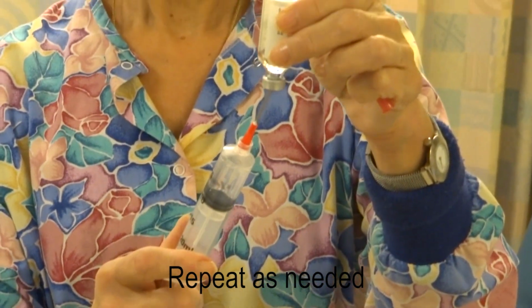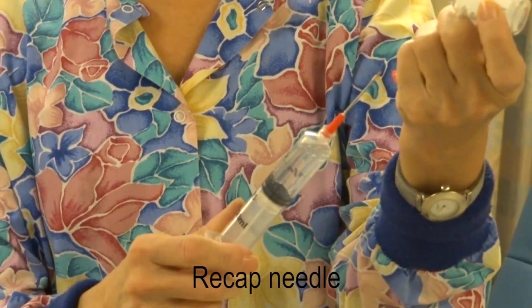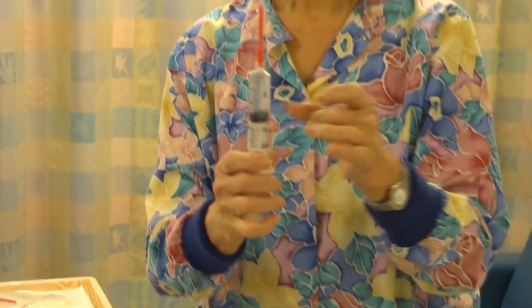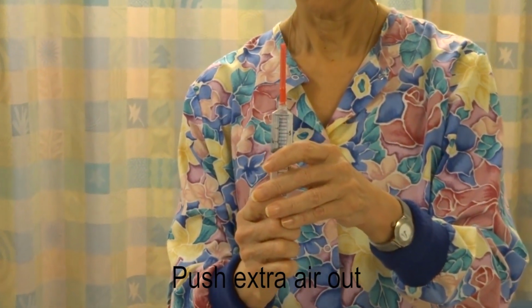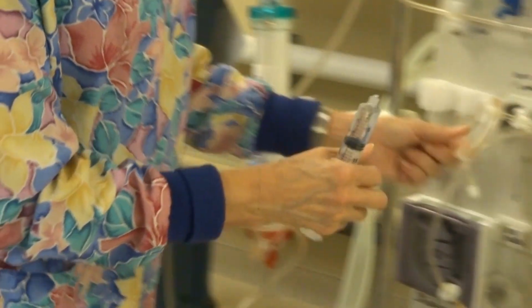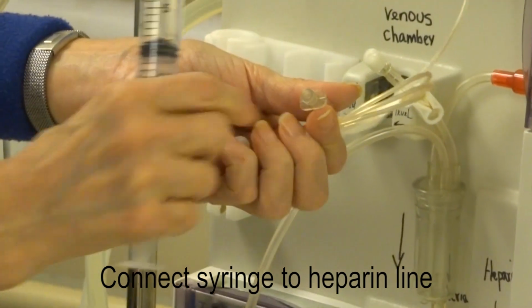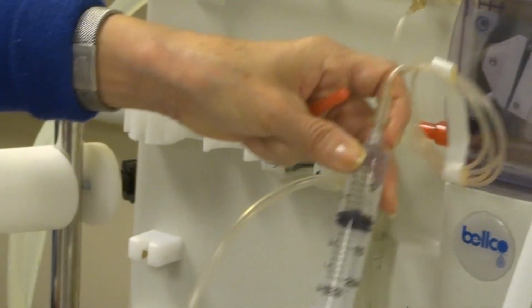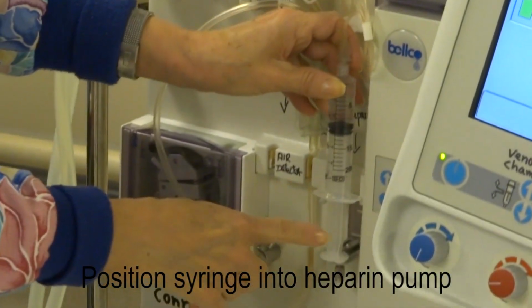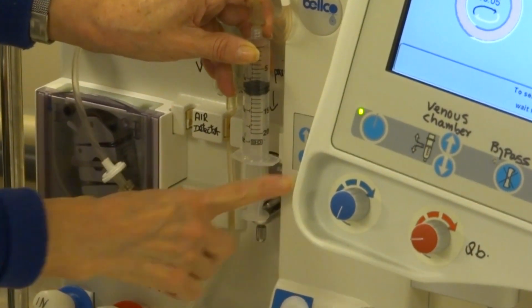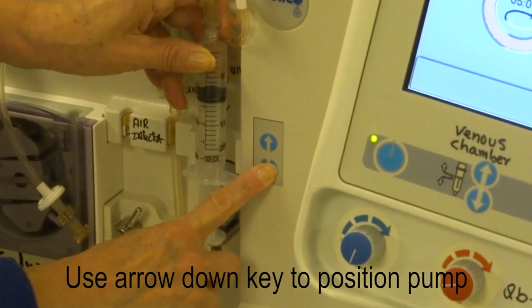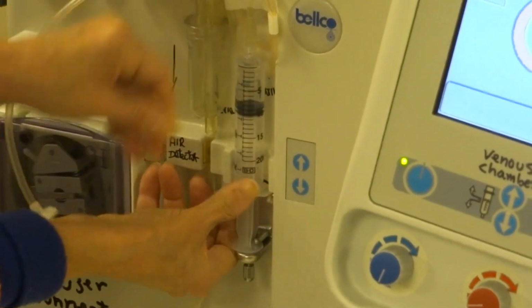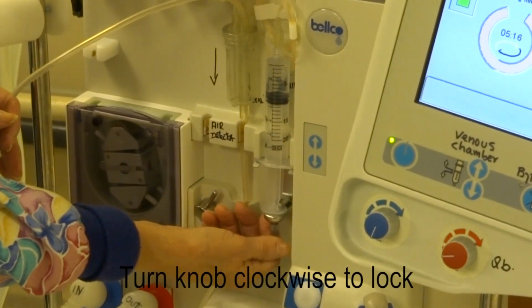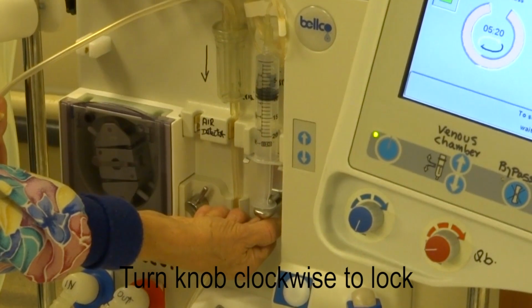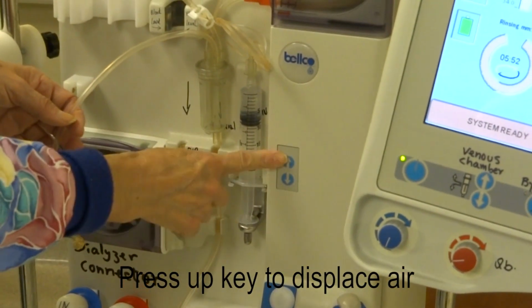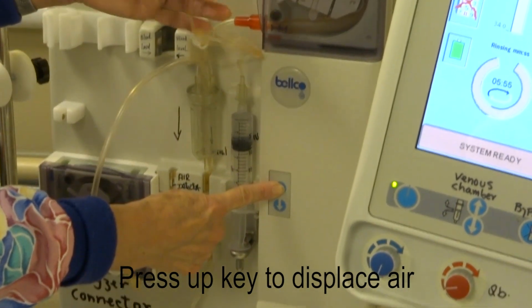You might need to do this a few times. Once you finish, recap the needle. Push the extra air out. Disconnect the needle and connect our syringe to the heparin line. Position the heparin syringe in the heparin pump and use the arrow down key to adjust the pump. Insert our syringe and turn the knob clockwise to lock the heparin syringe. Use the arrow up key to displace the air that was in the heparin line.